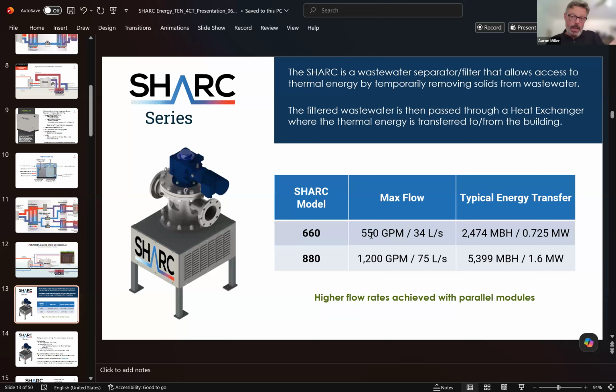The baby SHARC can handle 550 gallons of raw sewage a minute. Our big system, the 880, as you can see, can handle 1,200, and we can stack these side by side. For instance, I'll talk to you in a bit about this project out in Vancouver, where we have five of our 880s side by side, filtering 6,000 gallons of raw sewage every minute to provide hot water for 23 million square feet of indoor space in Vancouver, right?